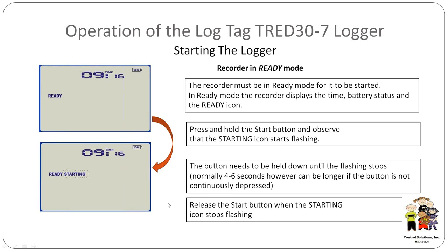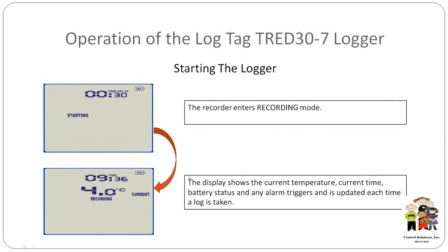So that bottom button that we just looked at, we're going to start the starting sequence, and the stopping sequence is exactly the same. So by holding down the bottom button in the ready mode for a 4 to 6 second period of time, the starting word is going to flash on and off, almost like a signal light. Starting, starting, starting. And when the starting word becomes solid, this has indicated a completion of the starting sequence. You're going to remove your finger immediately, and it's going to go into a recording mode.